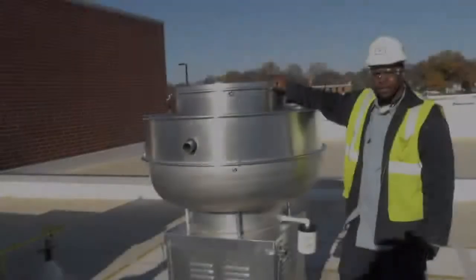And you said the 60 degrees there, that's outdoor ambient temperature, but then your supply is 70, correct? Correct. And I guess 70 is going to be the maximum you would ever see in the space? Is that what you're saying? Coming from our supply plenum, that's correct. And it will not turn on. This is basically telling it how cold does it need to be before I turn on.